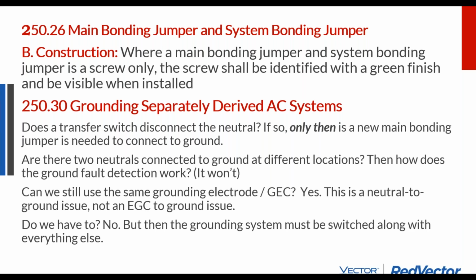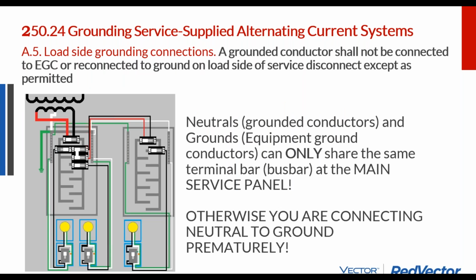Says where a main bonding jumper and a system bonding jumper is a screw only, the screw shall be identified with a green finish and be visible when installed. So often these sub panels will come with a screw that you can put into them that will connect the neutral to ground right at the panel itself. And so you may get a panel delivered to you and it may have a green grounding screw. And the difference is, is it the main panel? Is there already a neutral to ground connection being made ahead of the green panel, like in an external disconnect switch or the utility meter itself?